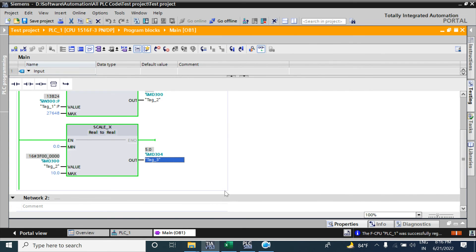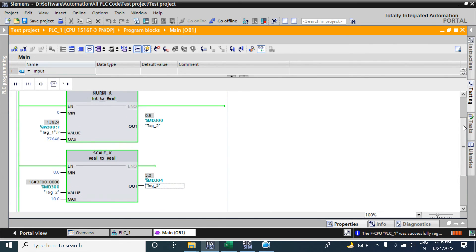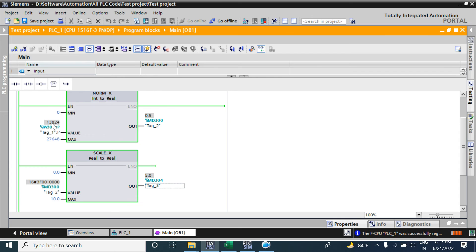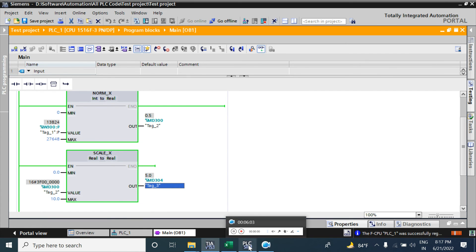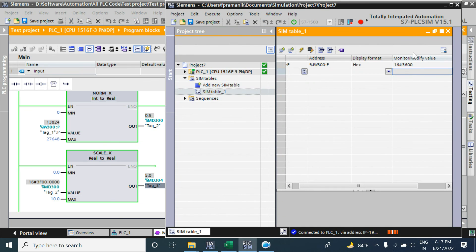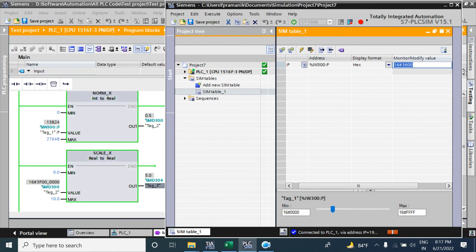So here also I will see in as a floating point. Now if I force, already it's forced to 50 percent of this measuring range, that is 13824. So if the pressure range is 0 to 10 bar, it is now 5 bar, 50 percent of this range. Now I will force by another value.